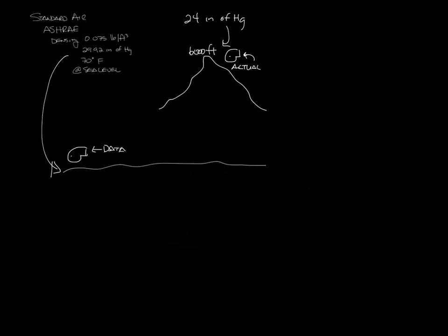Let me make a little bit of room here. Okay so I've shown the load equation several times before. It's Q equals 1.085 times CFM times delta T. And I usually say that 1.085 is a constant, but technically it's only 1.085 at standard air. It's actually the product of density and specific heat.